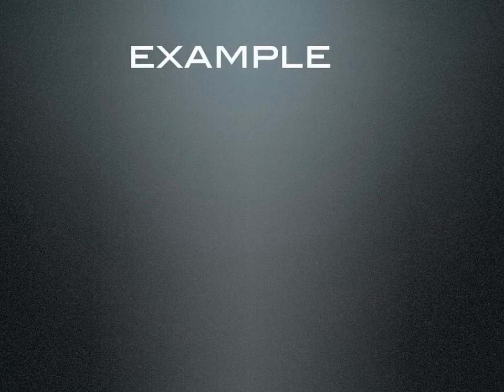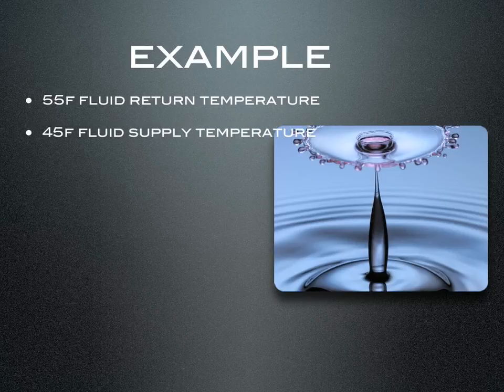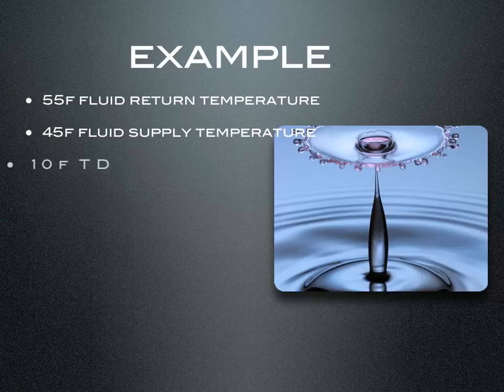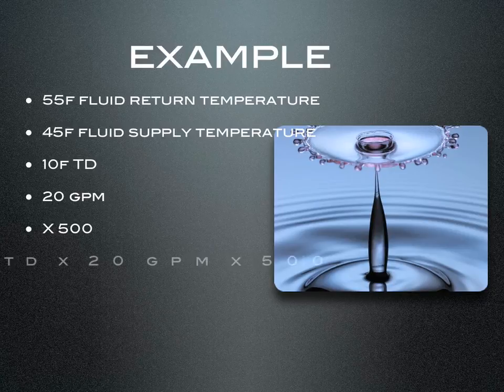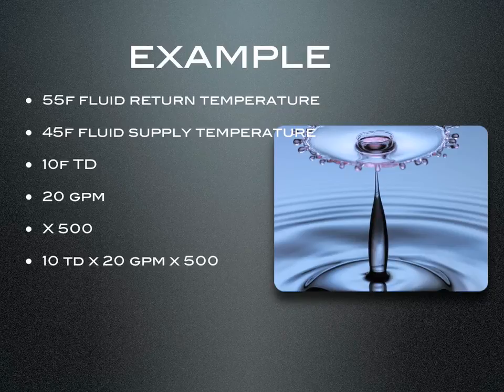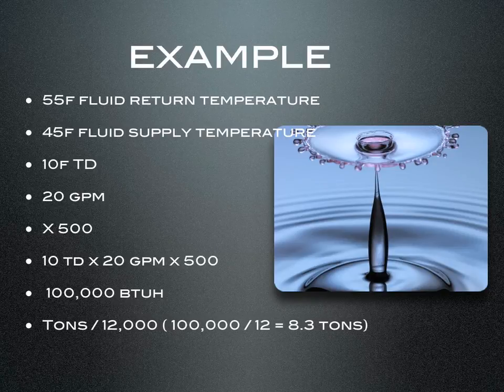Let's make sense of what I just spoke about. You'll have 55 degree fluid return temperature back to the chiller, and 45 degree fluid supply temperature back to your process. So that's going to be a 10 degree temperature difference. You have 20 gallons per minute and your constant for water. If you take those three factors — 10 temperature difference times 20 gallons per minute times 500 — you'll come up with 100,000 BTUH. If you want to convert that into tons, you would just divide that by 12.